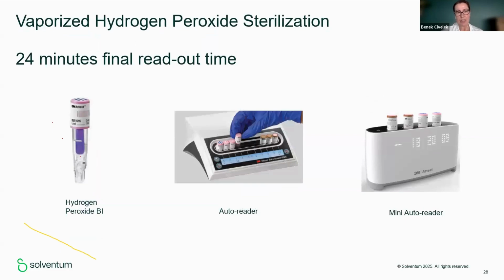For hydrogen peroxide, the same technology is there, and again you can use the auto readers and another type which is called the mini auto reader to have your results in a shorter time. While choosing the indicator, the indicator technology, certification, and performance are very important, but at the same time we have to consider the technology of the auto reader, because the auto reader should also prevent human error. Whenever you are not successful in crushing the media, if the media cannot see the spores, the auto reader should inform you and warn you, because if you don't crush and the media doesn't see the spore, even if the sterilization is not successful, you cannot have the right result. So when talking about biological indicators, we always consider auto readers because they are a full system and they are validated with each other.